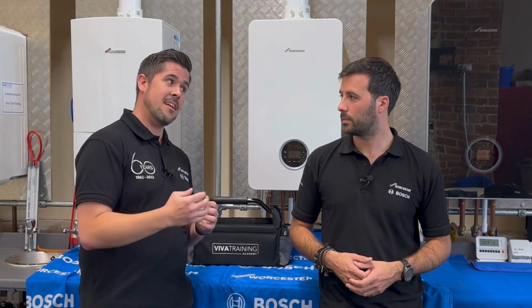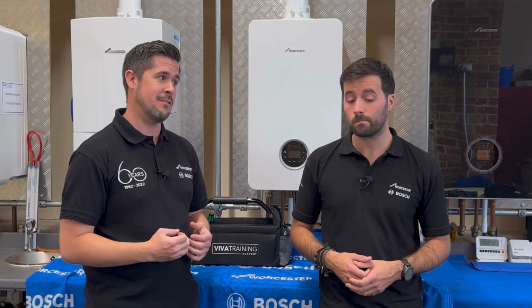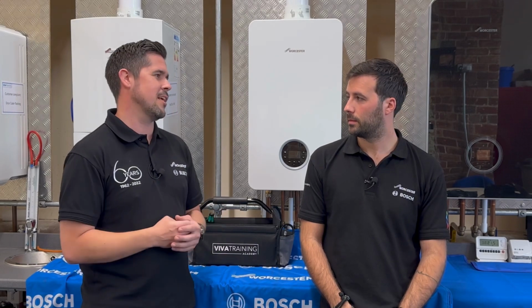The first part of a call for me is always to speak to the customer, asking them things about their system and the fault, trying to relate those questions to the fault they're reporting. So that can be anything like, if it's a hot water fault, is it just from one tap or all the outlets that are affected? Is it one radiator or all the radiators? At the end of the day, the customer lives in that house 365 days a year, and they know that system like the back of their hand. The reason you're there is because something isn't quite right. So ask as many questions related to the fault as possible.